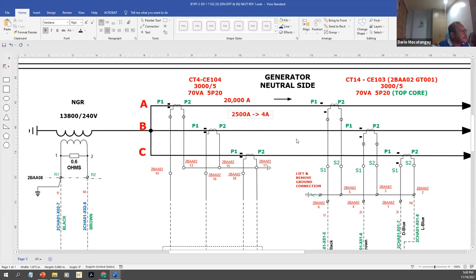So the relay is set at 5 amperes. And this is just basic, you know. Okay, so 4 amps is below 5 amps, so it's not going to trip, right? Now, let's say there's a fault. So 20,000 amps will flow. So 20,000 amps divided by the CT ratio, which is 600, that will be 33 amps, right?